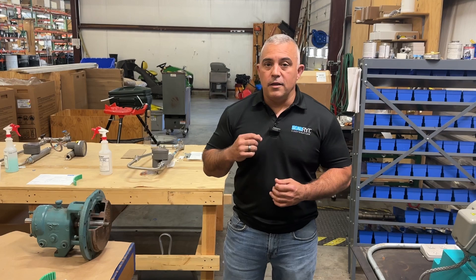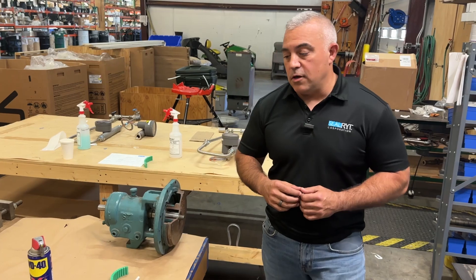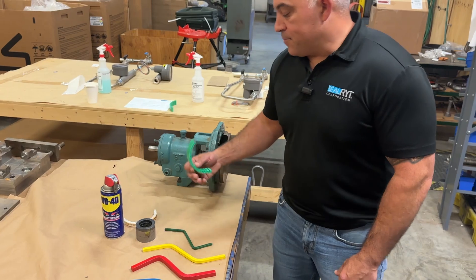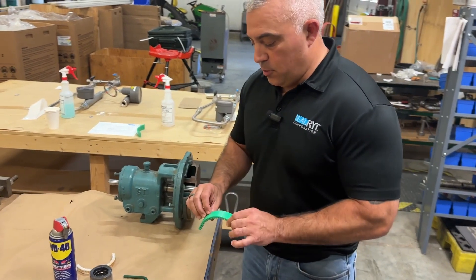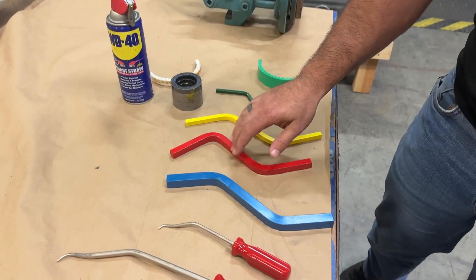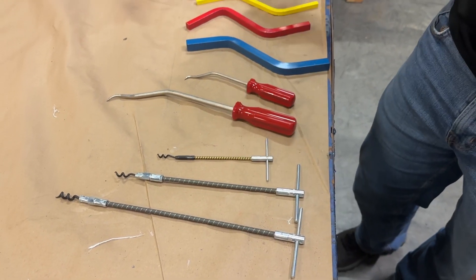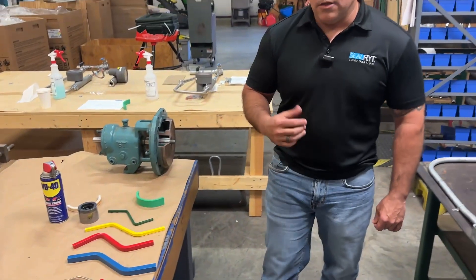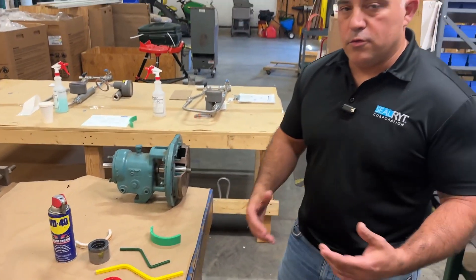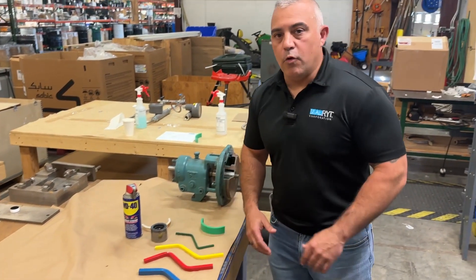There are several different tools on the table to properly install and remove packing. Starting from my right: this is the lantern ring. This here is a pusher tool. This is a setting tool — all three of these are tamping and setting tools. The O-ring pick, and these are our extractors right here. You just have to make sure before you do your installation or removal that you have the appropriate size equipment for what you're going to be working on.